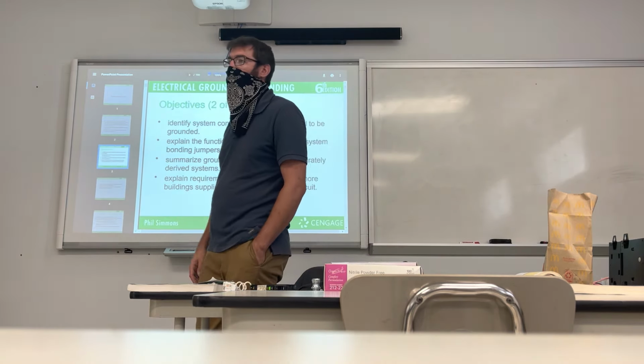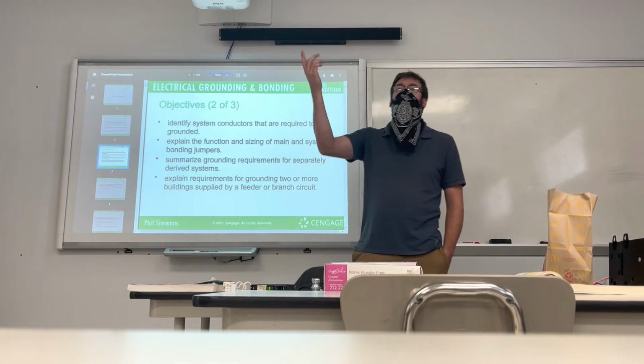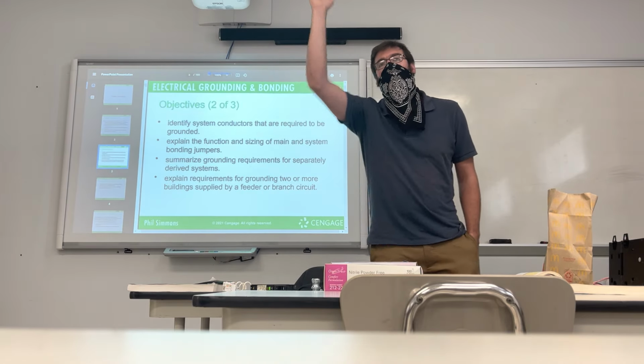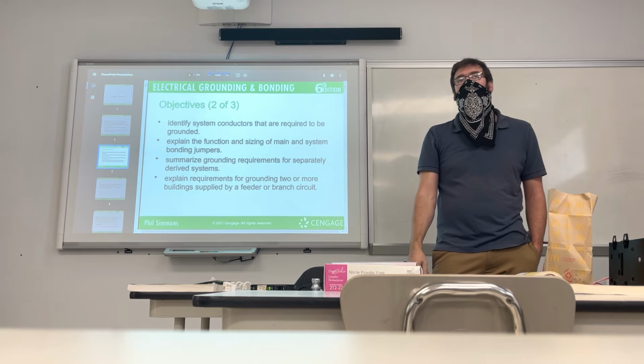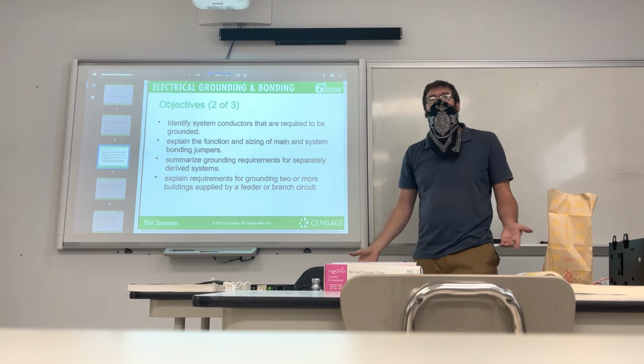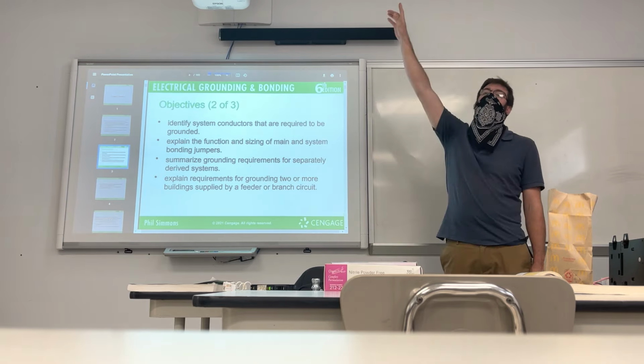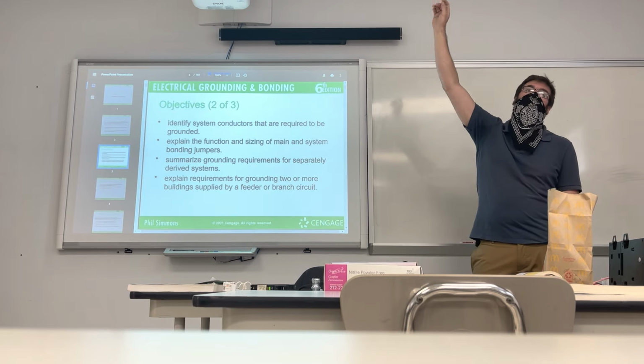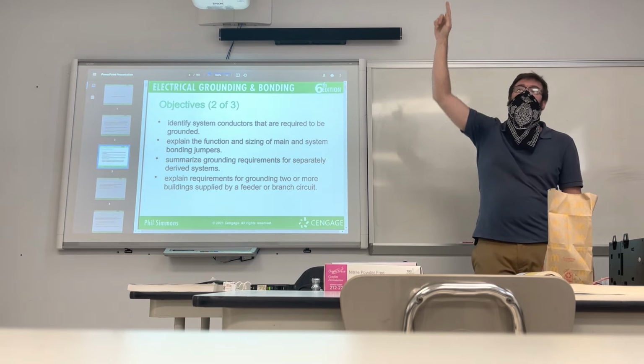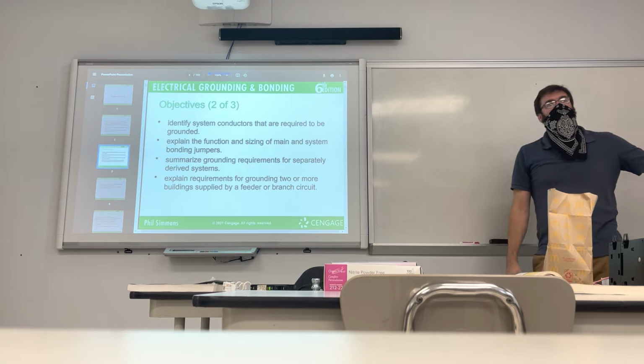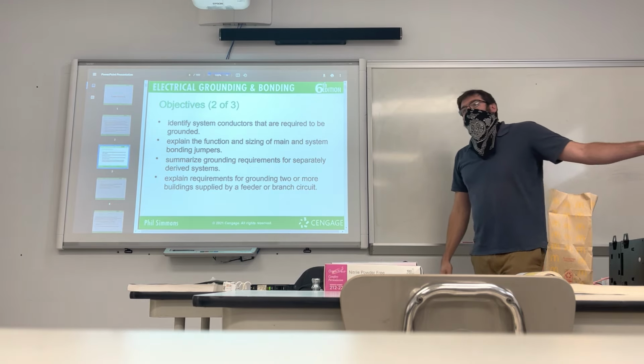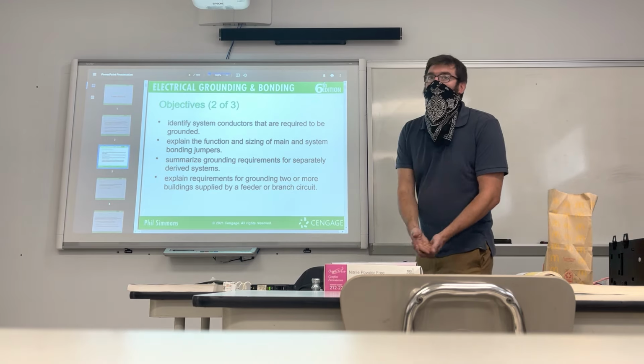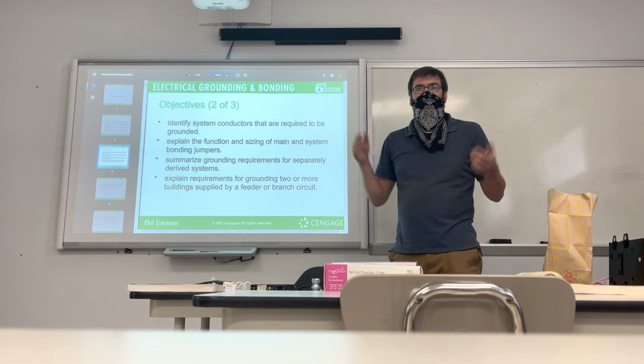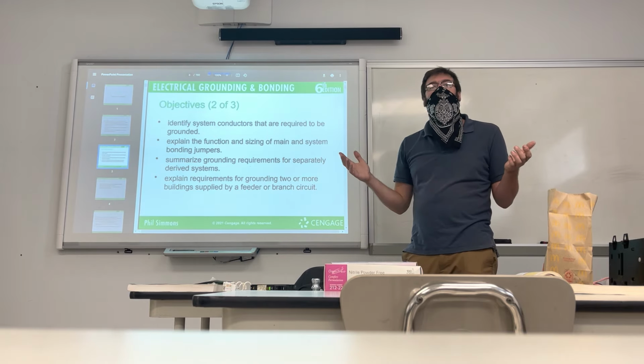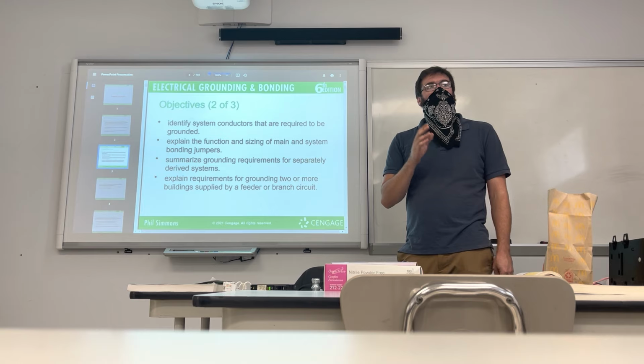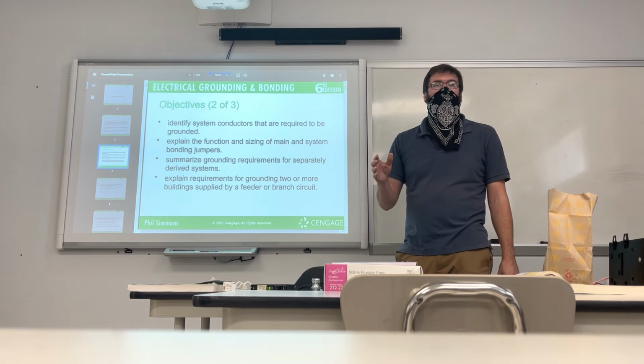Transformer. Right at the transformer, right? If there's a transformer hanging on the pole, you will see a copper line chasing that pole down to the ground. And they bury that copper line with the pole. So that transformer is where the neutral comes off of that transformer. It's grounded right up there. And the second it comes into your house, it's grounded in that main panel box, all right? And that's the conductor that has to be grounded, right? The neutral conductor. Just think of the neutral conductor. Don't even call it neutral in your head from this point. Grounded conductor.